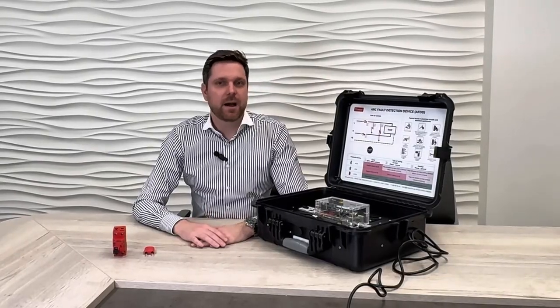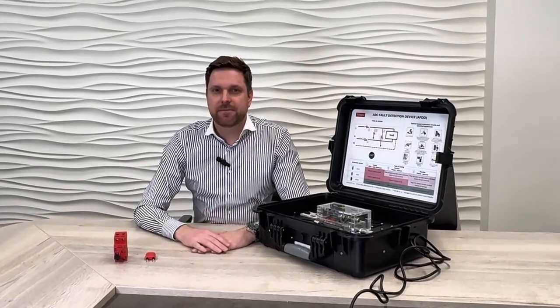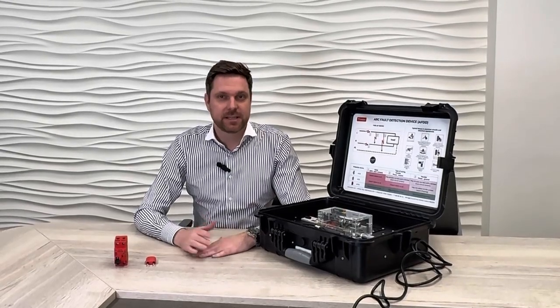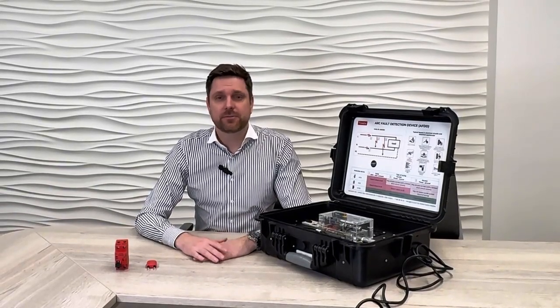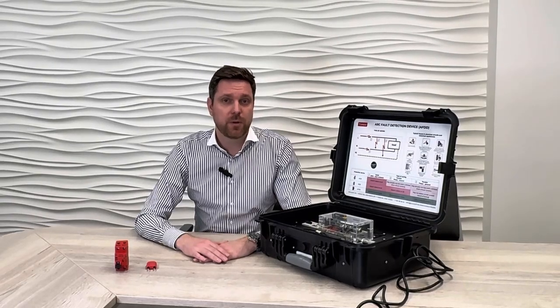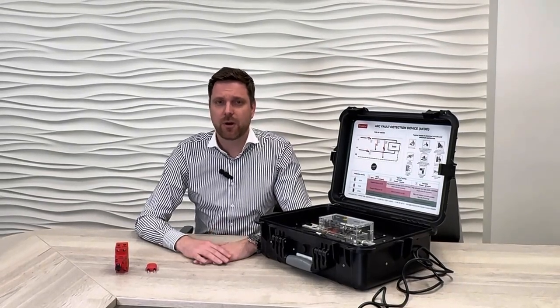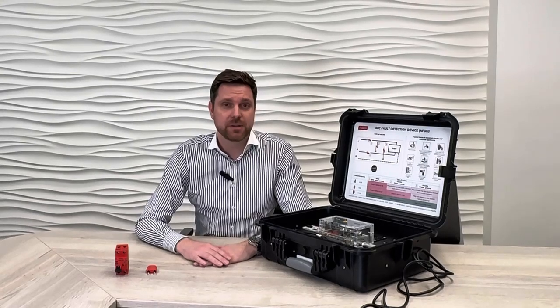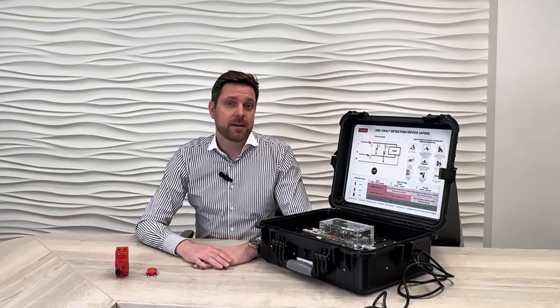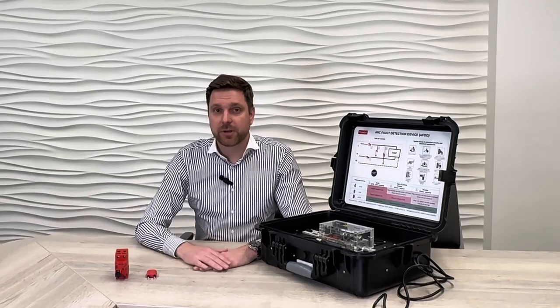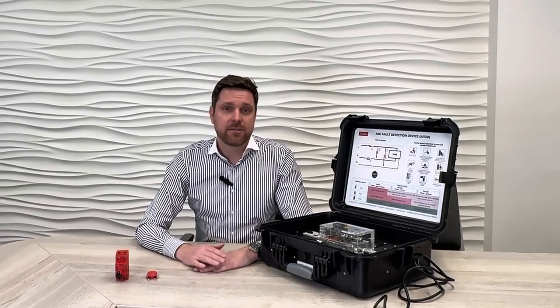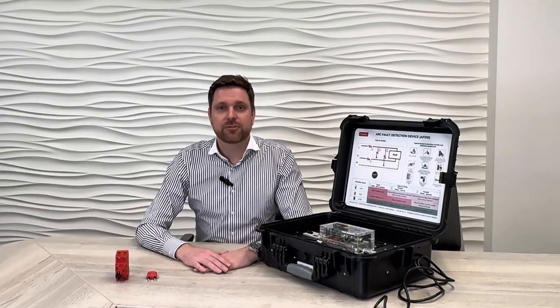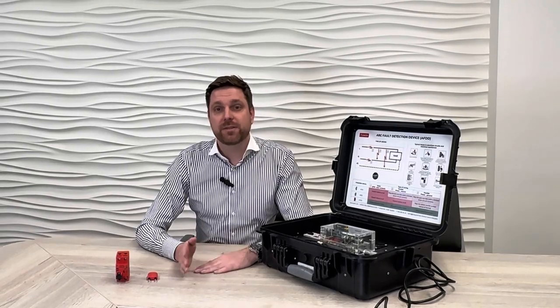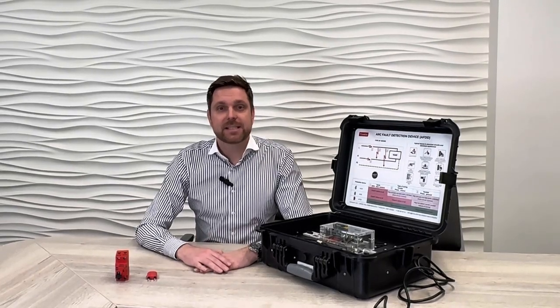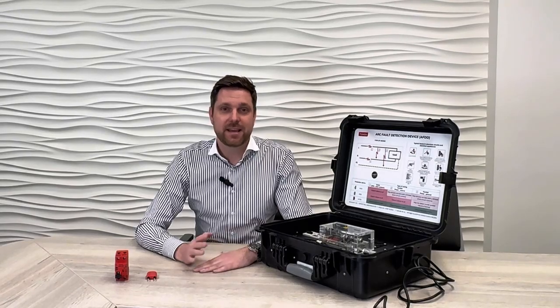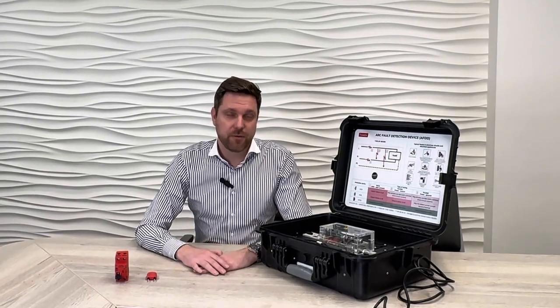But wait, you might ask, why do we need AFDDs if we already have MCBs and RCDs? Great question. Here is the deal. Traditional protection can't always spot arc faults caused by loose connections, old insulation, or damaged cables. No overcurrent or current imbalance, no cause for alarm. AFDDs are the third step in the evolution of electrical protection, joining forces with their older siblings, MCBs and RCDs, to create the unbeatable trio of safety.